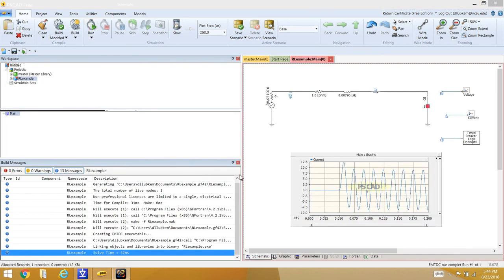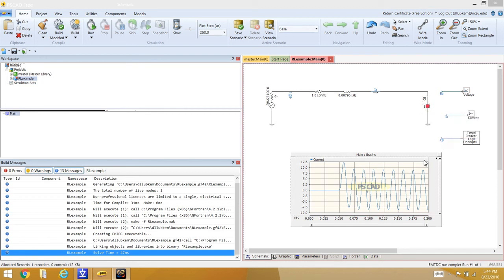After debugging, it was found that a three-phase circuit breaker had been placed instead of a single-phase one. This was corrected by replacing it with the single-phase circuit breaker model.